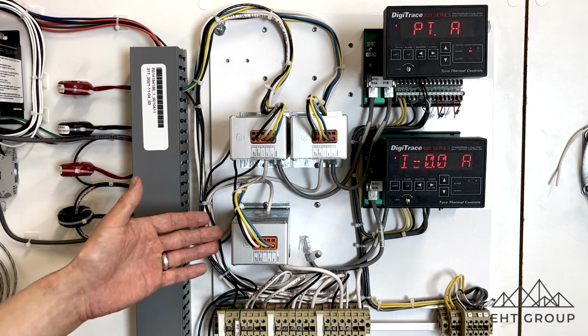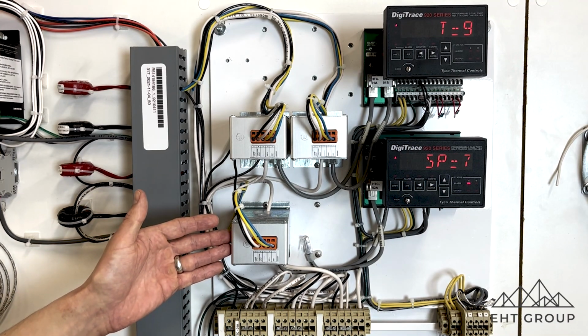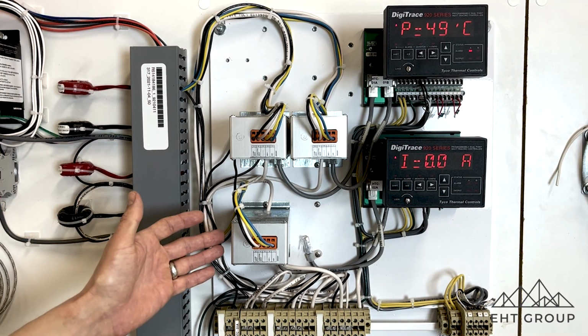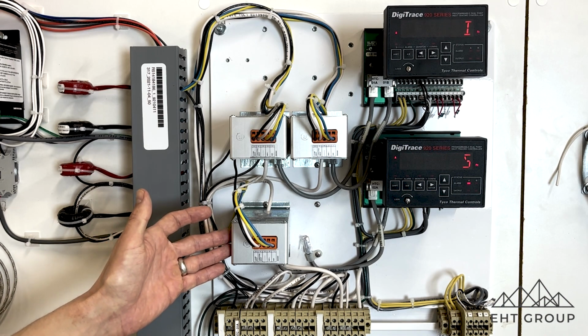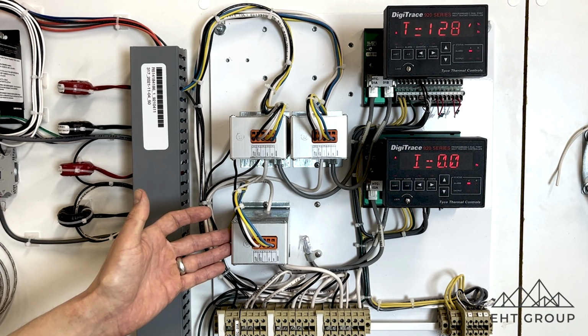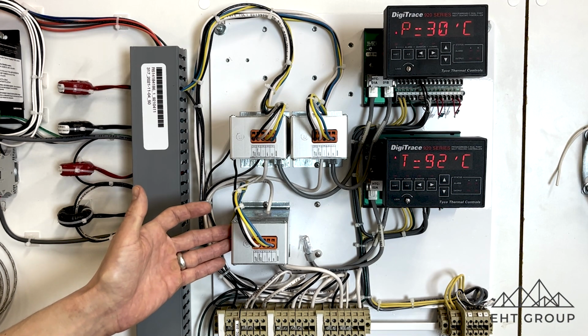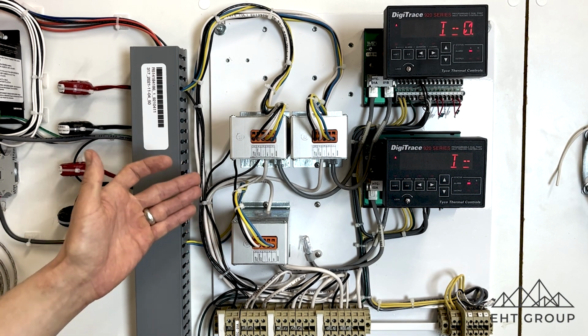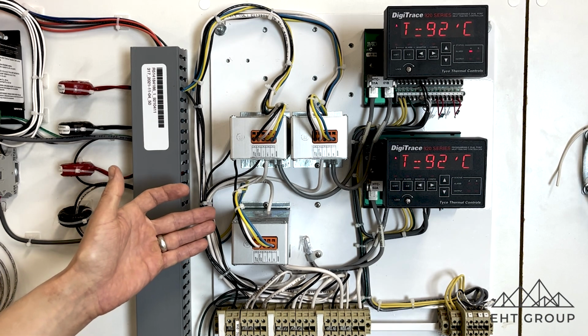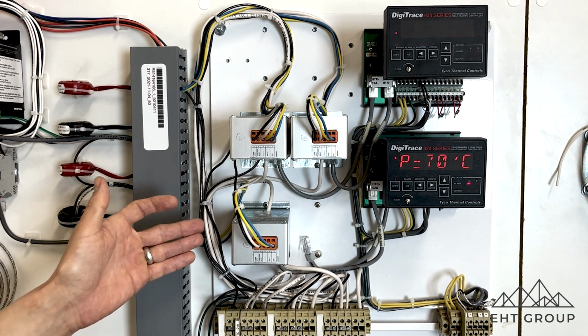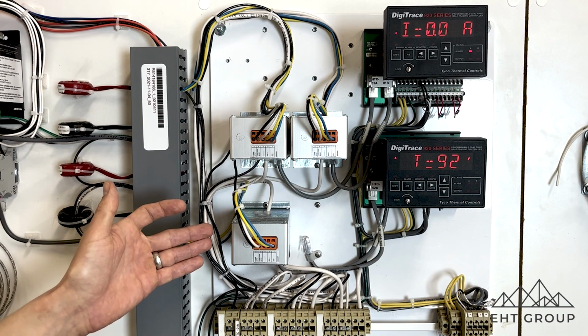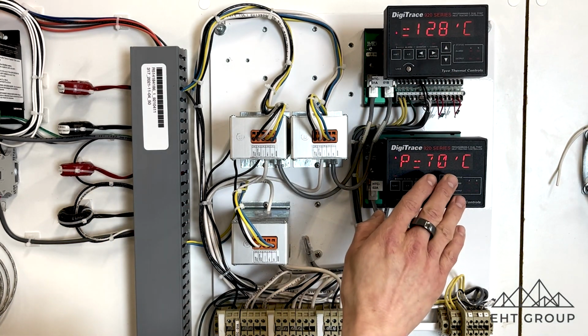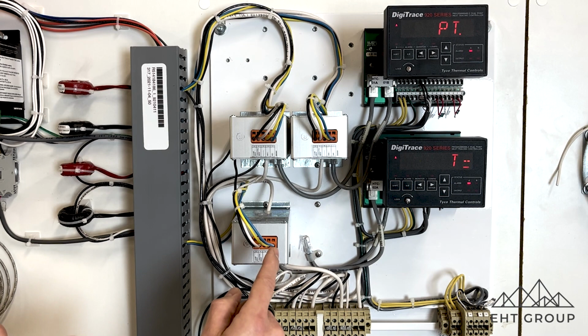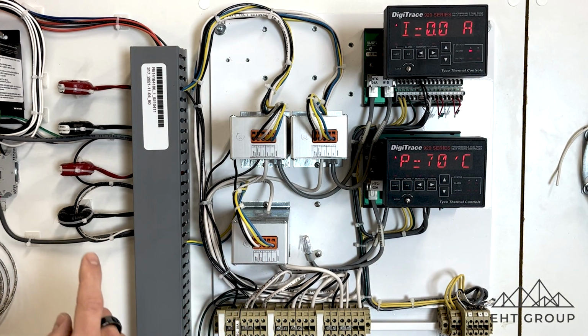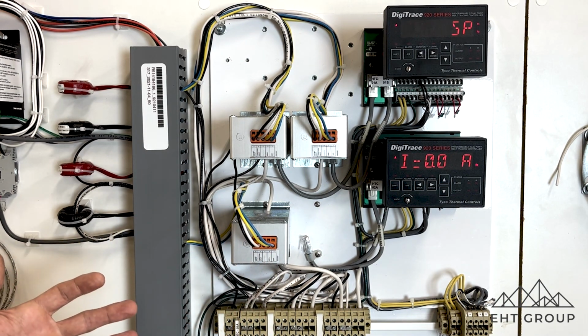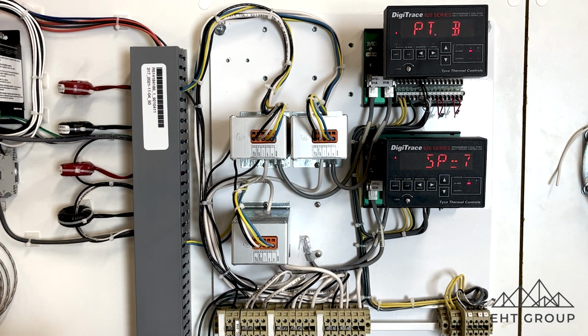Now, these modules, I'm going to start with these guys. These are the 920 current transformer modules, and these things do much more than a typical CT. Not only does this module read, or measure, current from the heat trace circuits, but it's also used as the control power to our heat trace controller modules, and it's also used to do the switching for either a solid state relay, which is most common, or an EMR or a contactor.